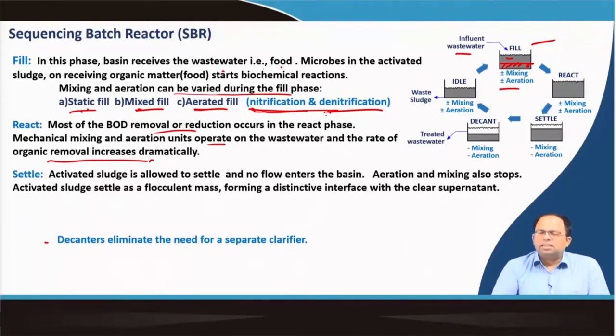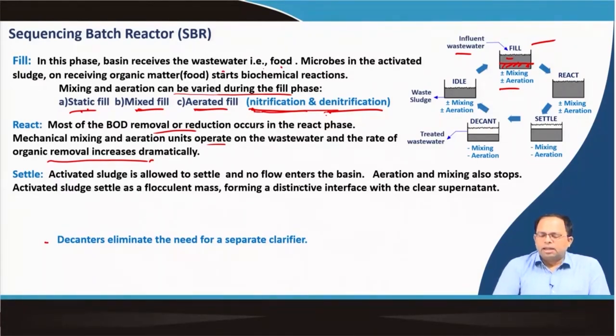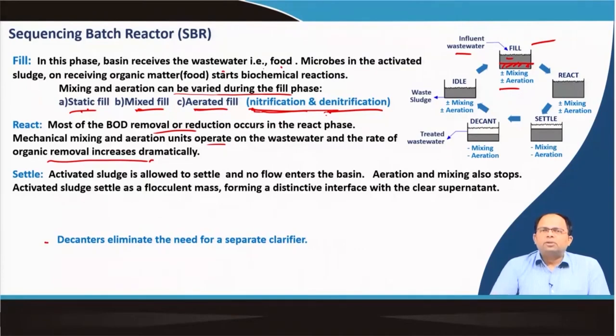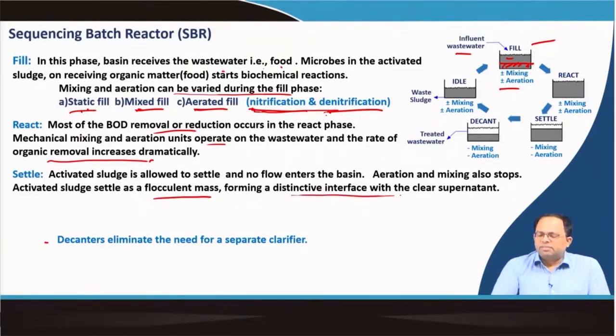Once the react phase is completed and most of the organic matter has been consumed, we have the settle phase where activated sludge is allowed to settle and no further wastewater is allowed to enter the basin. With no mixing and no aeration, the sludge floc settles as a flocculant mass, forming a distinct interface with the clear supernatant — you can see the gray matter gradually settling down with clear liquid at the top.